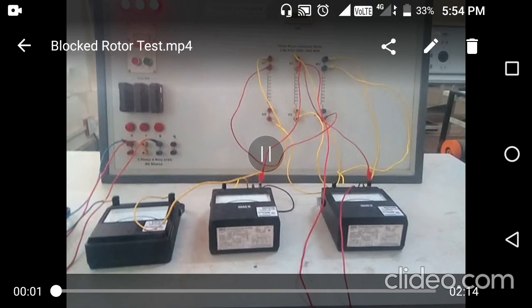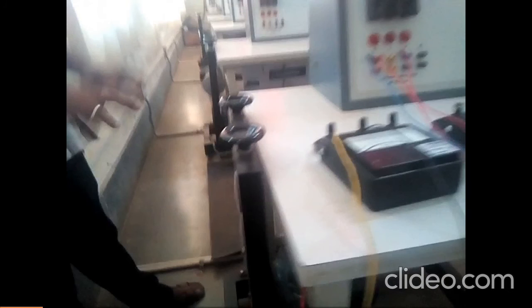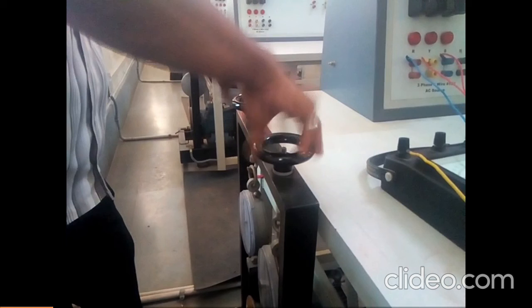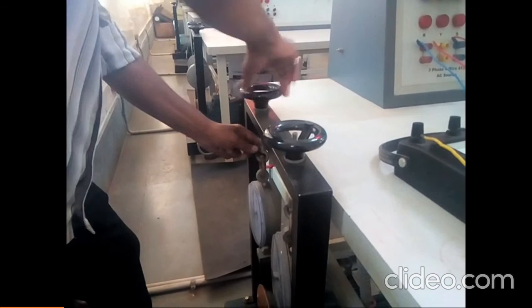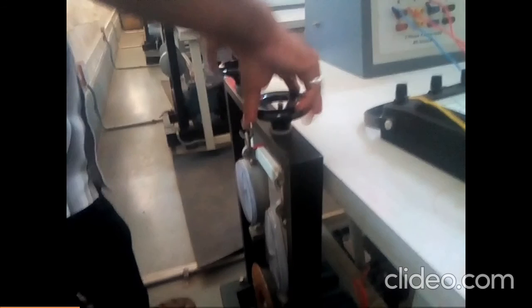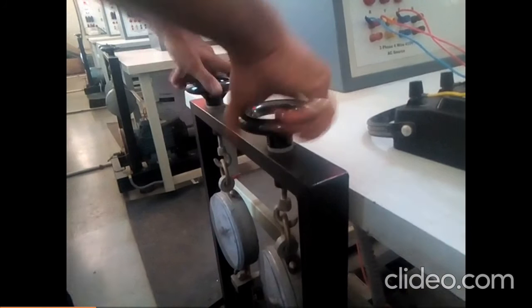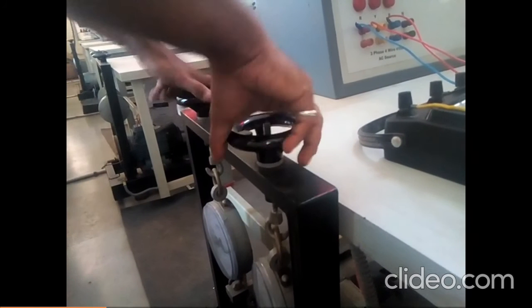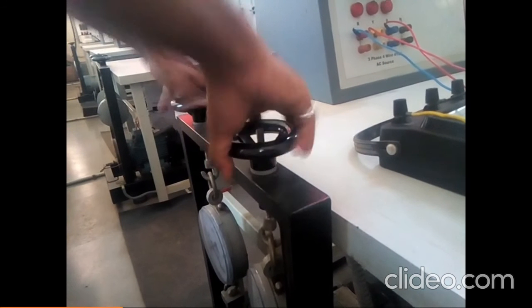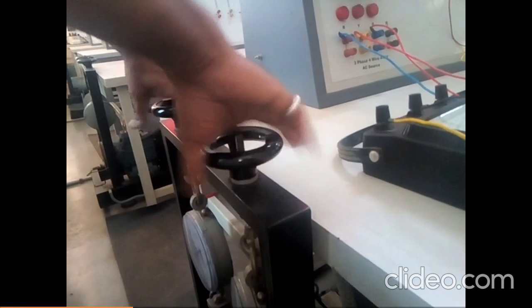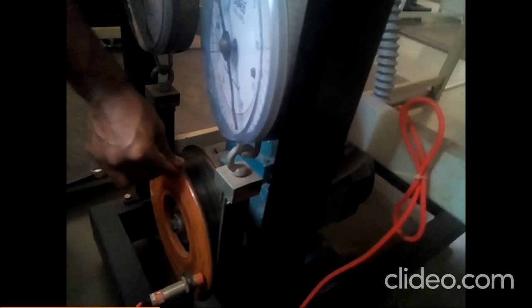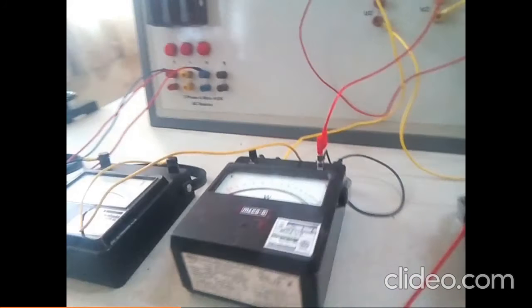The connection diagram is the same for both the no load test and the block rotor test. The first step for the block rotor test is to block the rotor of the three-phase induction motor using a belt and pulley arrangement. You can observe how the rotor is blocked. A pulley is coupled with the shaft of the induction motor, that is the rotor, and a belt is connected using adjustment. We can observe that the rotor gets blocked, and we can check it by hand.